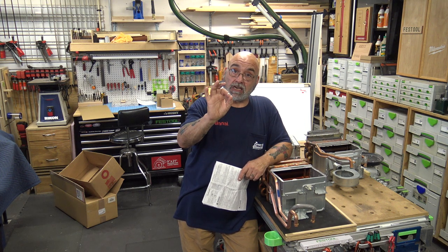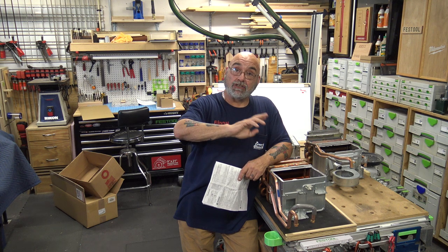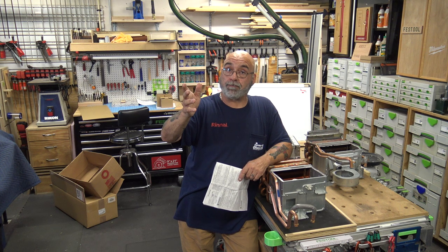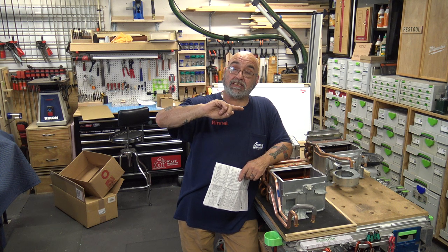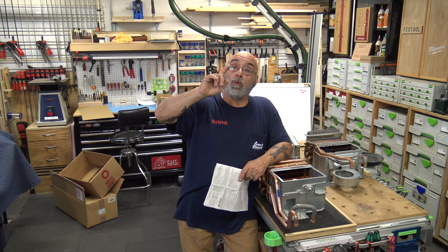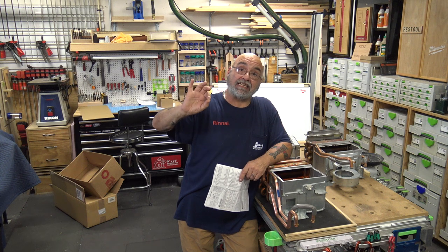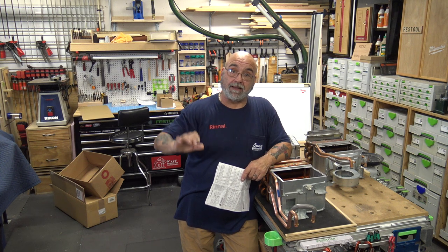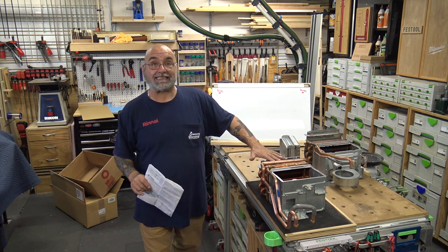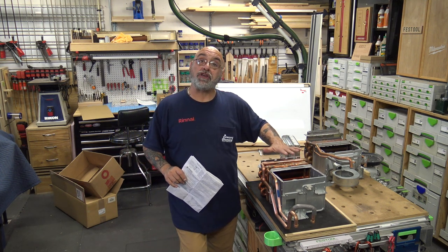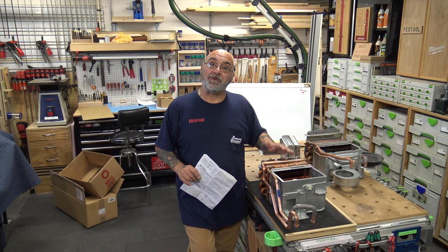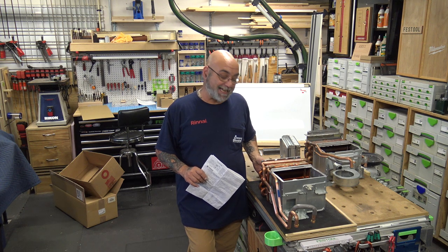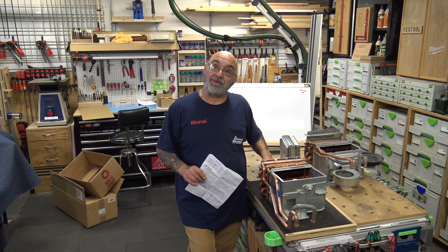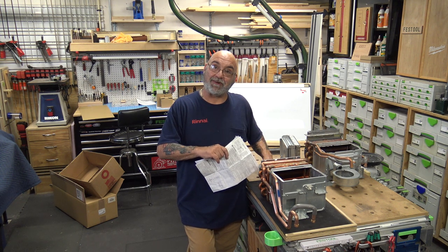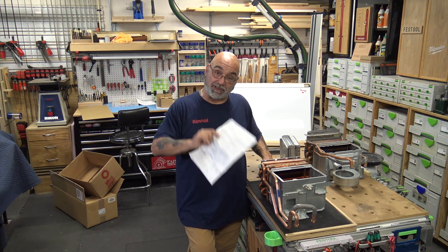Non-condensing uses metal inside, condensing uses plastic. The Sensei series has plastic inside and plastic outside, or what it says PP in the model number, or on the box it says for condensing tankless units only. If you put the plastic on a non-condensing unit, you will melt the plastic and it will get down into the actual air intake. And there's your first problem.